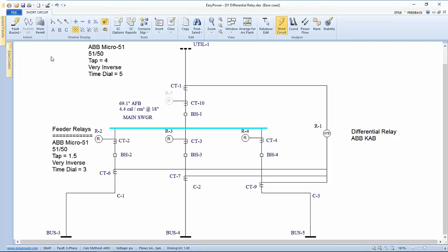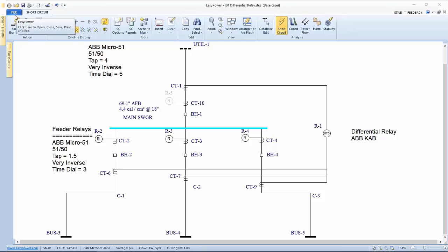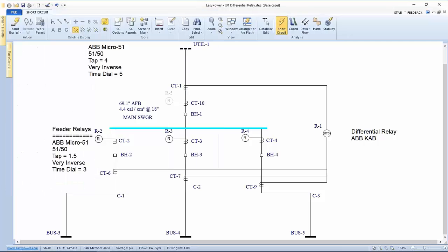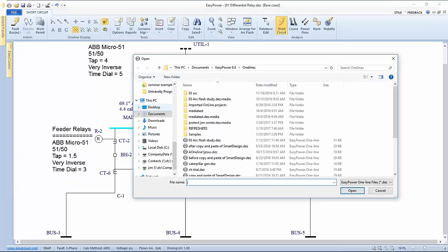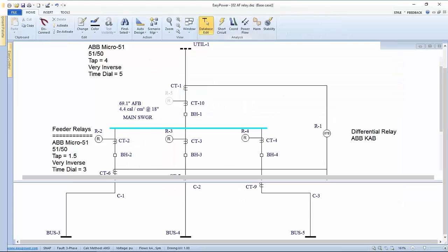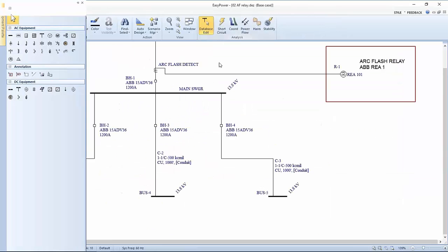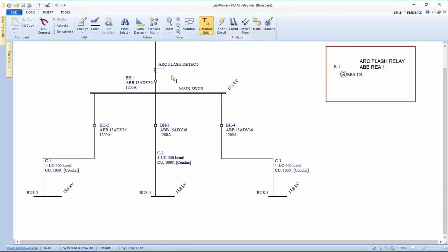The same theme is something that's handled on an ongoing basis, and it comes up in a similar way with the arc flash relay. This is the way a differential relay is set up in Easy Power. Next, we're going to do the arc flash relay. Let me open up that example. This is a little different in that the relay involved, while it's sensing the light on each of the buses that it's going to be covering, there really does not need to be an electrical connection other than to the trip unit that we're connected to.